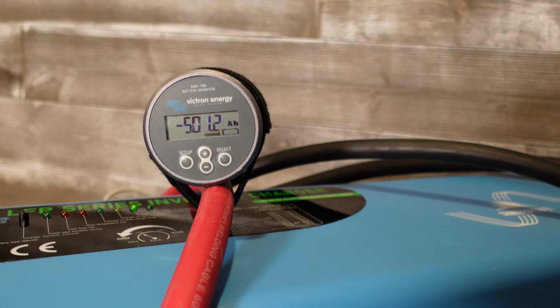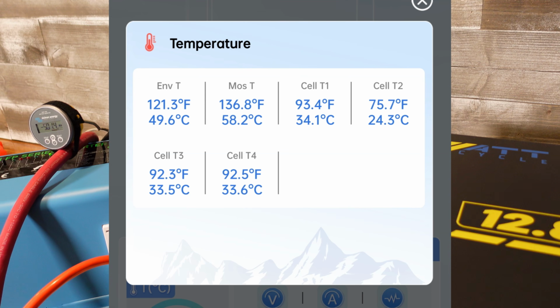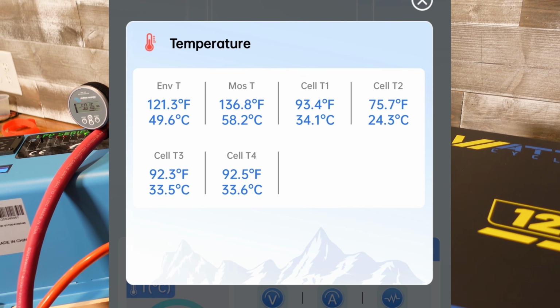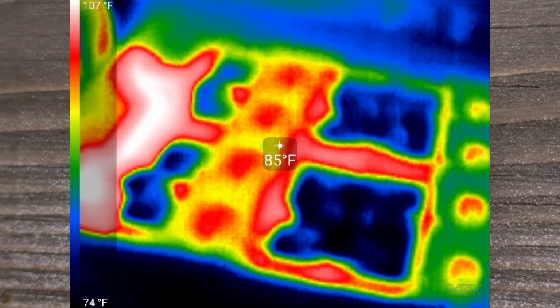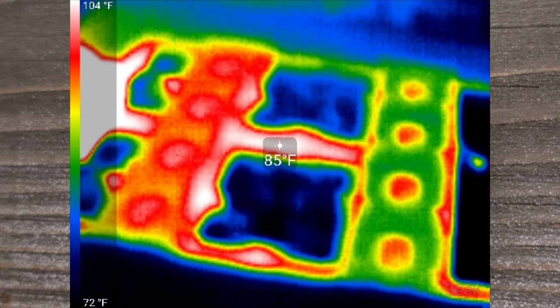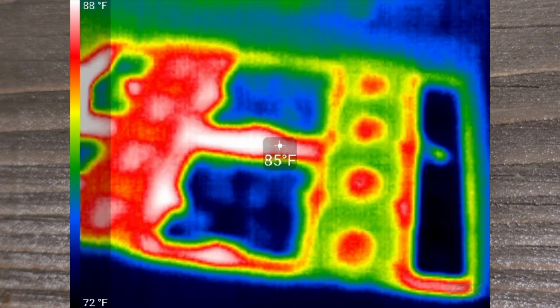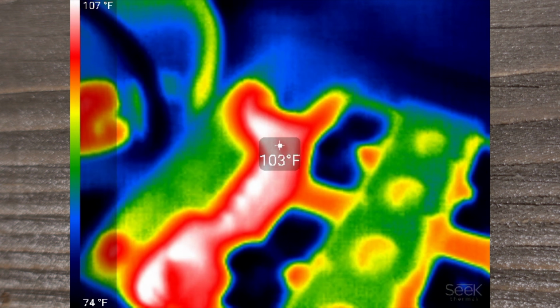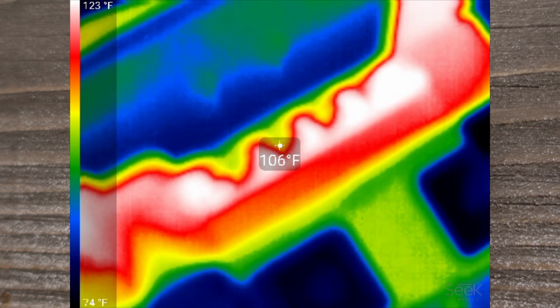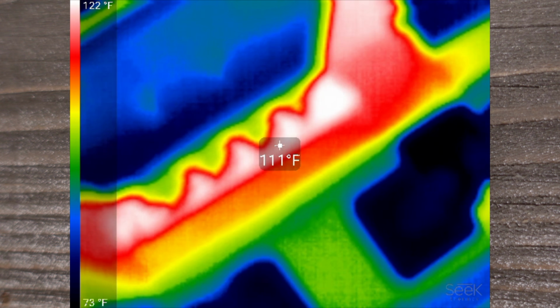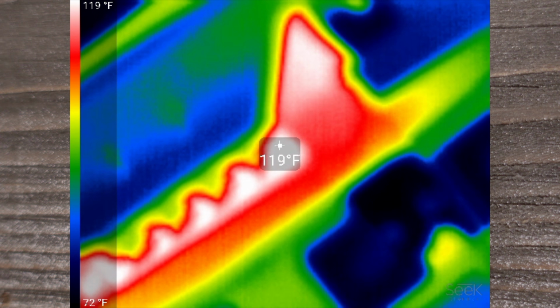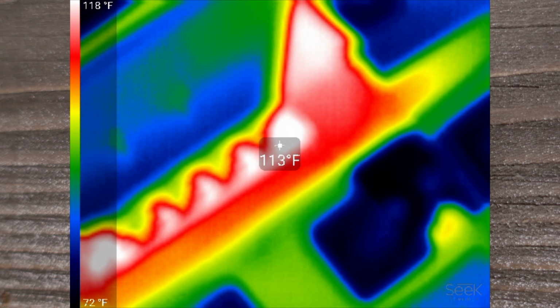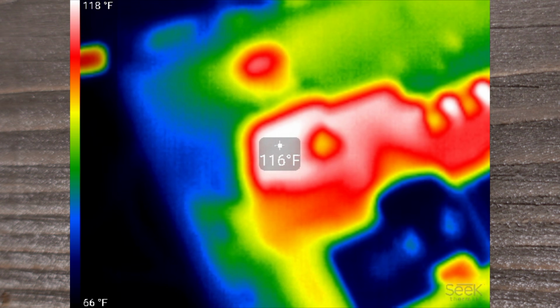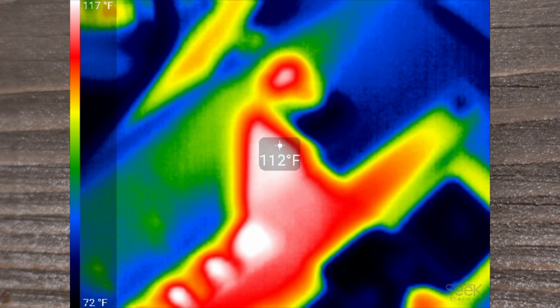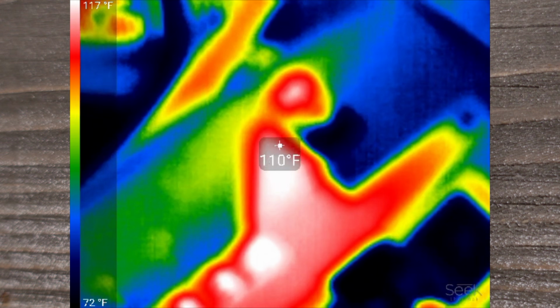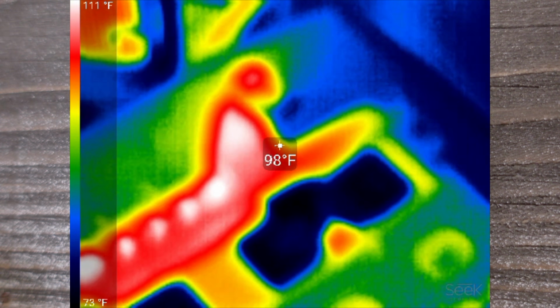So we've pulled 50.12 amp hours from the battery and our hottest temperature is sitting at 137 degrees on the MOSFET temperature sensor. Taking a look at the battery itself, we're still seeing peak temperatures around 85 to 86 or so degrees in there. But the hottest part is definitely in the front where the BMS is. So this is looking down at the side of the BMS here, and the hottest temperature I'm seeing is 119 degrees on the screw terminal. So that's the main negative post at 116 degrees. And here we have the positive lead to the positive post. A little bit cooler. It looks like that's peaking around 112 degrees. So there's not too much to see in here.